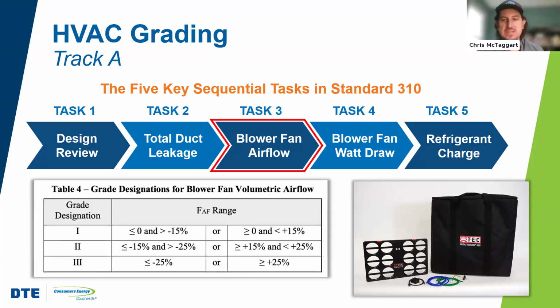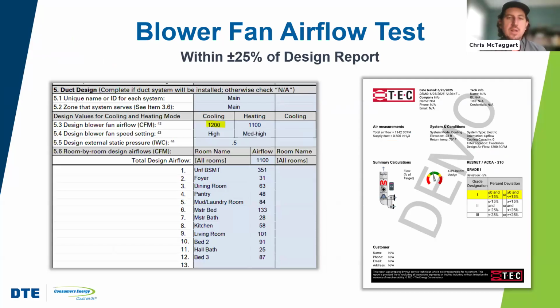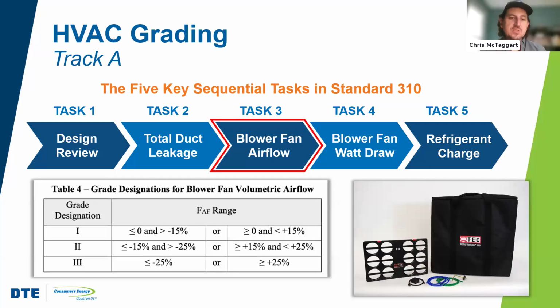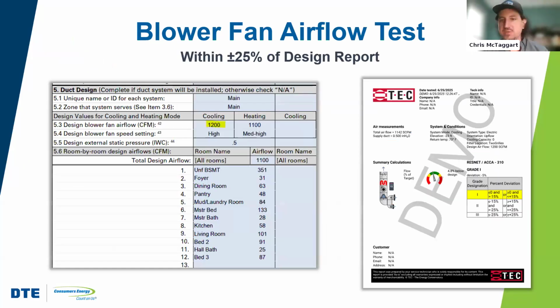of the design flow. There's a lot of different ways to measure the blower fan airflow, but using a flow grid system created by the Energy Conservatory is probably one of the more direct ways of doing so, but there are several other methods. So for the purpose of Energy Star, we can either be grade 1 or grade 2. So you can actually have a 25% deviation and still be acceptable for Energy Star, but certainly you get more credit in the energy modeling if you are a grade 1. So, the way this works is you go with the higher of the airflow rates. So in this instance, it's the cooling airflow rate.